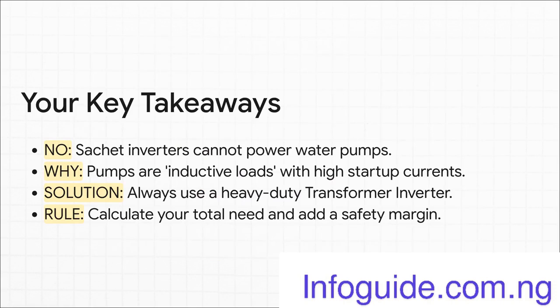So, if you only remember 4 things from this whole explainer, make it these. 1. Do not use a Sachet inverter to power a water pump, just don't. 2. The reason why is that pumps are inductive loads and that startup current is a killer. 3. The solution is to get a proper heavy-duty transformer inverter. And 4, the golden rule: do the math to figure out what you need, and then add a nice big safety margin on top.